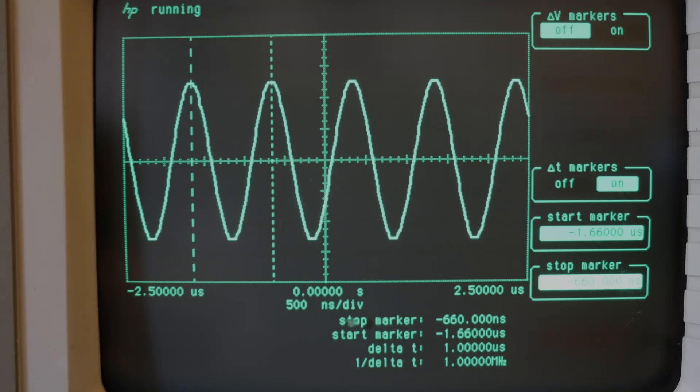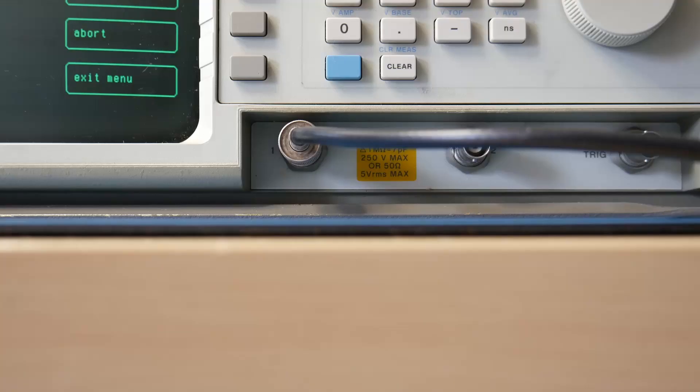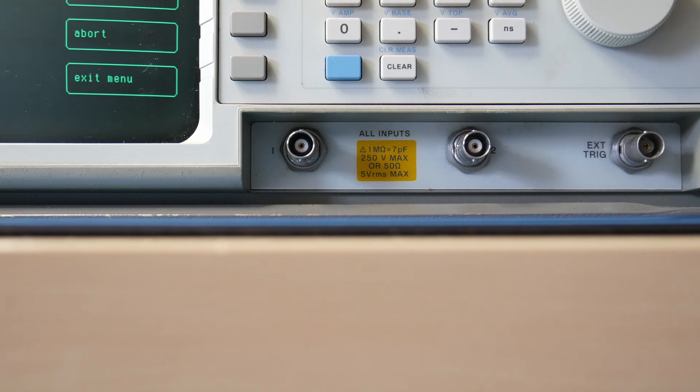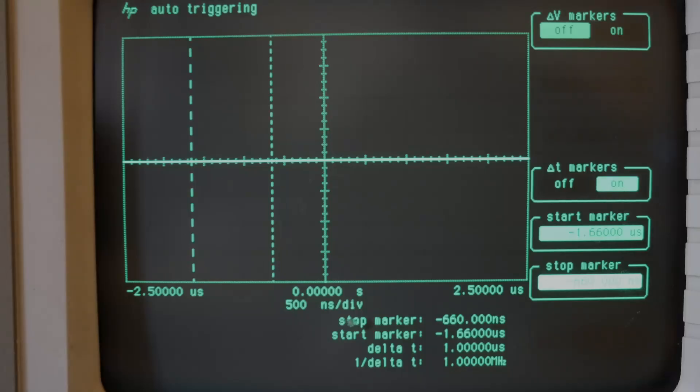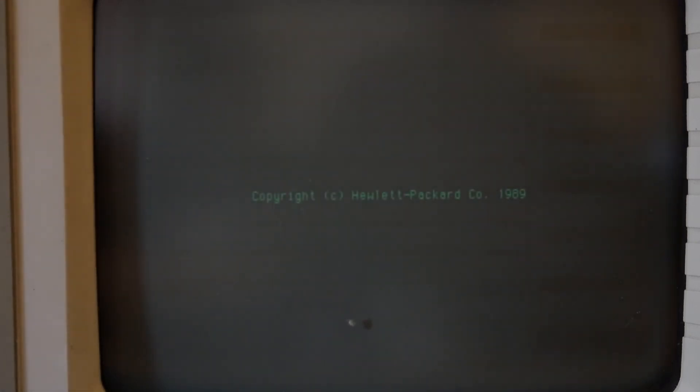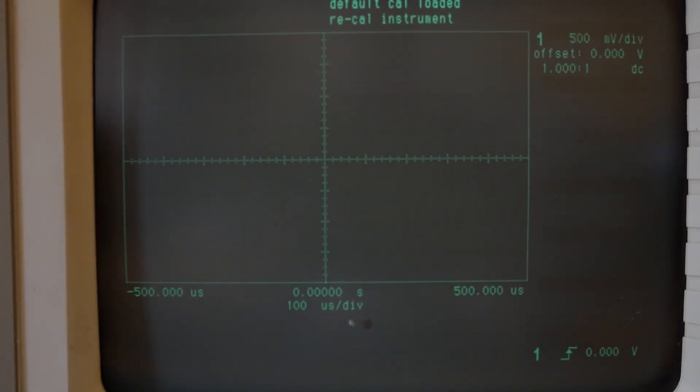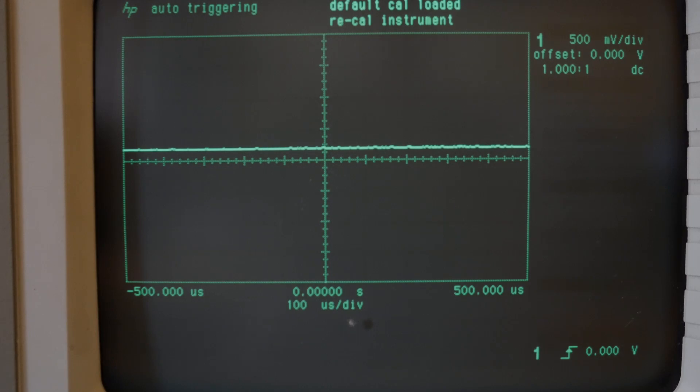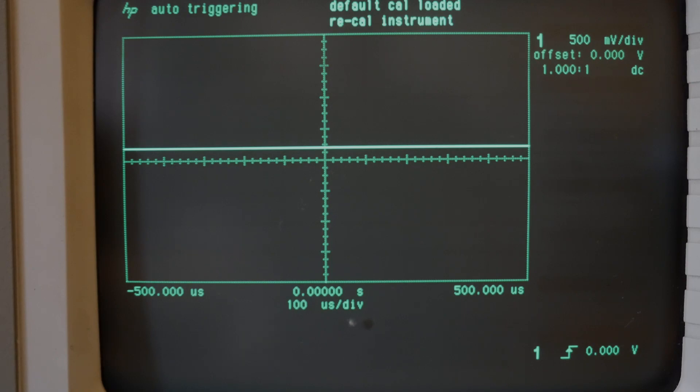Let's turn off the signal here and I'll turn off the device and reboot it here. So let's unhook the signal that goes to zero as you can see. I turn the unit off. Wait a second here and then turn it back on and we'll wait for it to boot up. And indeed it says default cal loaded recal instrument. So I do believe that calibration storage is where the problem lies. So let's look into that.